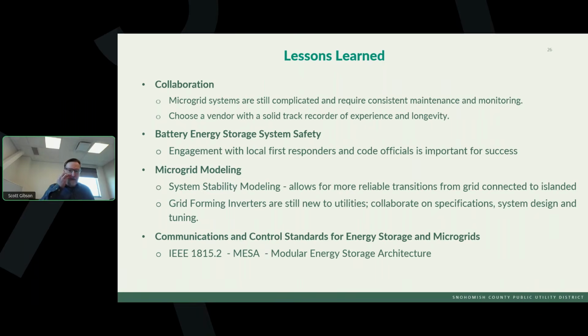You can take a battery module, put it into thermal runaway, drive a nail through it, whatever, and throw it in the ocean - the fire might be extinguished, but the thermal runaway will keep going. If you pulled it out of the water, it would just burst right back into flames. It has to run out of all its fuel before the thermal runaway stops. Putting water on it doesn't stop it. So safety is incredibly important.